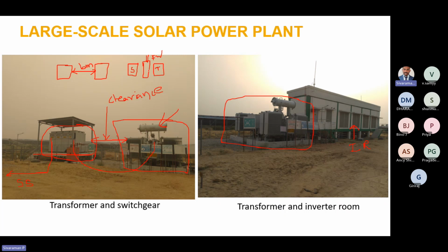Okay. So this kind of firewalls will be required where space is not available in many of the inverter locations. Space will not be a constraint because the solar PV system requires so much space. But in substations within the city, some substations where space is not available, those locations only firewall is required.